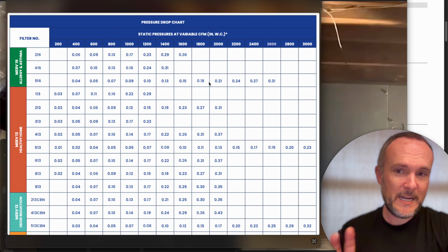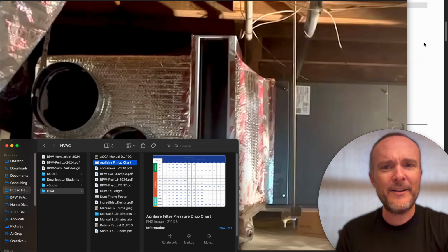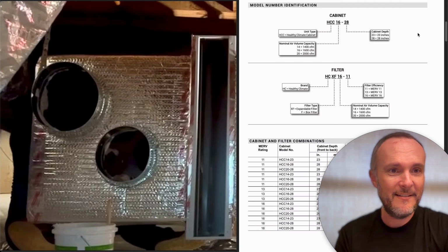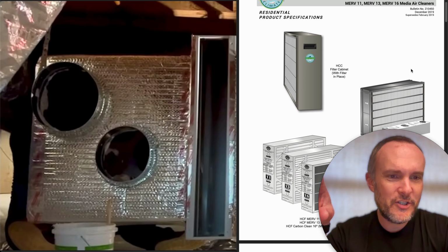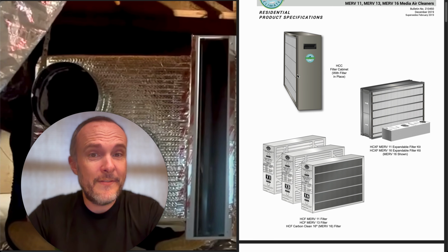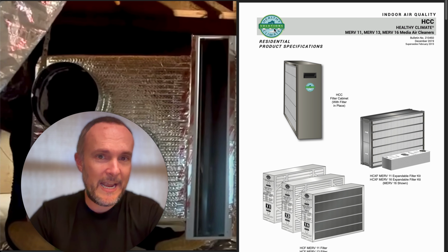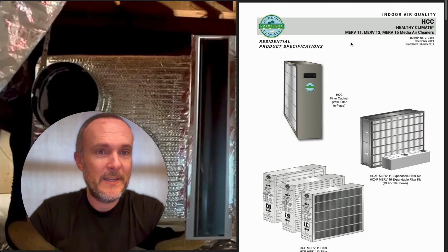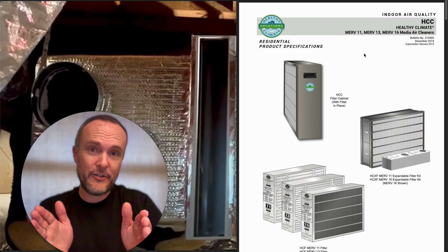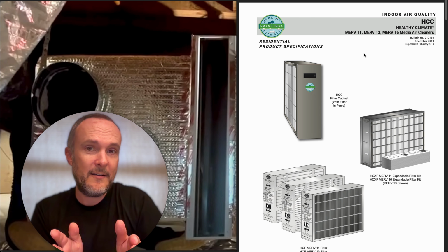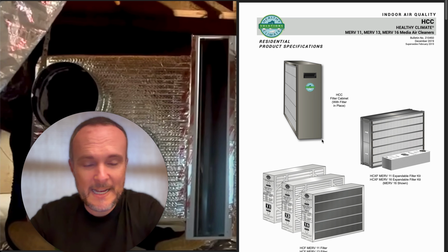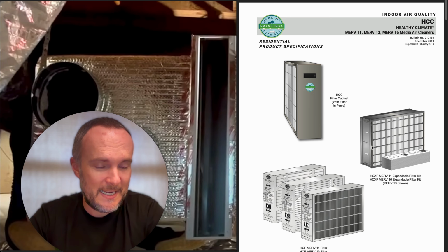Now, the problem comes in where we have a system that is not this that gets put in. And let me show you what this actually is. What I just saw on one of my client calls here is one of these. This is a Lennox product. It's called Healthy Climate Solutions. And they come in MERV 11, MERV 13, MERV 16. They're 5-inch thick filters, which sounds better than the 4-inch thick Aprilaires. And it has this hold in place thing. It's got gaskets and it's airtight and all the nice things.